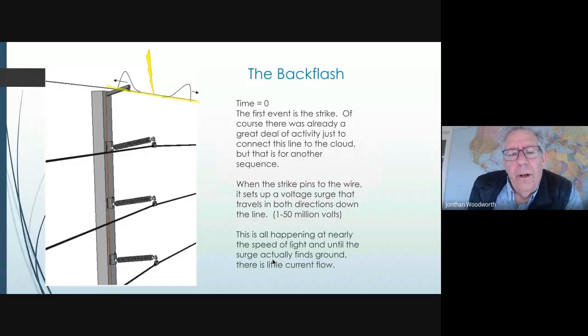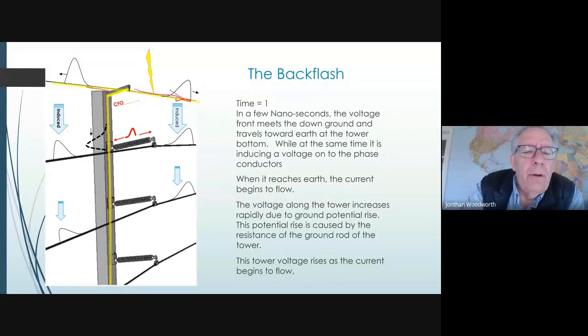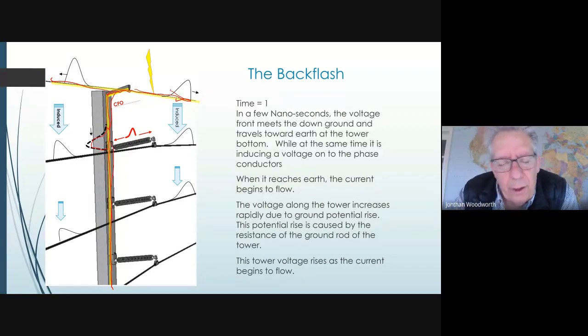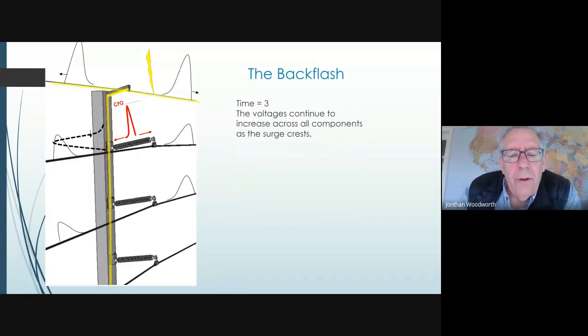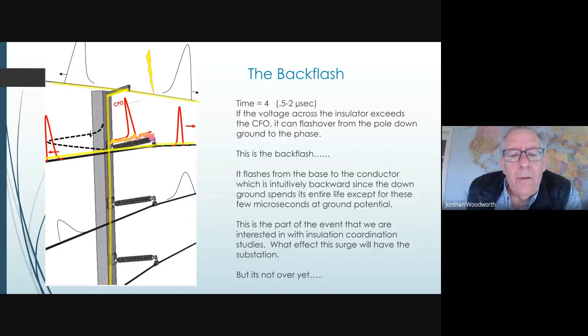In this sequence here, lightning strikes the line, and then it travels down the line. It travels down the shield, and it keeps traveling on the shield. But at every pole, there's this down ground connected to Earth, so the current starts to flow down the pole. But remember, now this has an impedance. There's a certain impedance in a line, and there's a certain ground impedance down at the bottom of the pole. So it can develop some very high voltages at the base of these insulators as the surge travels down the line. And the voltage at the base of the insulator can actually get higher than the voltage on the phase. So when the voltage reaches the flashover level and it's higher than the voltage on the phase, we have a flashover to the phase.